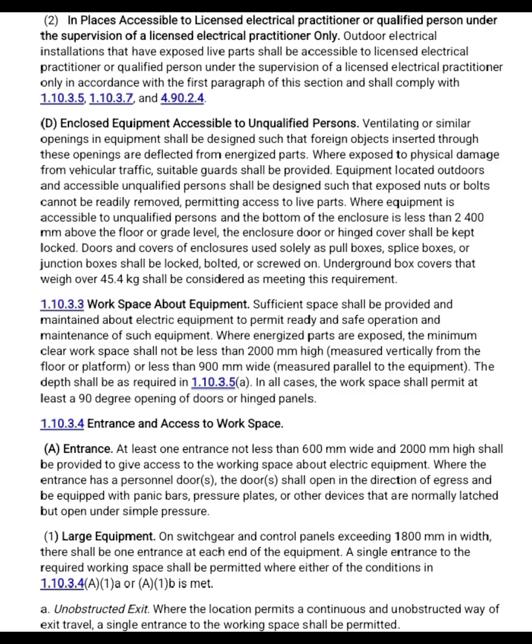In the workspace of electrical equipment, there must be enough space around the equipment for safe work. If live parts are exposed, the minimum workspace must be 2000 mm high and 900 mm wide. Doors should open 90 degrees for easy access. The entrance must be at least 1 and 600 mm wide and 2000 mm high.